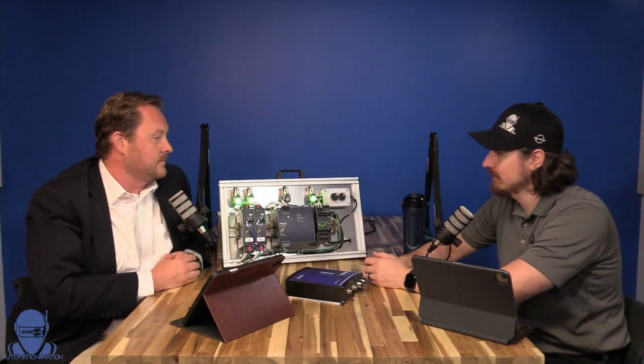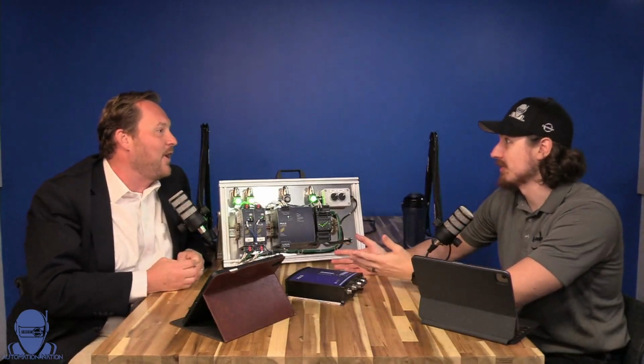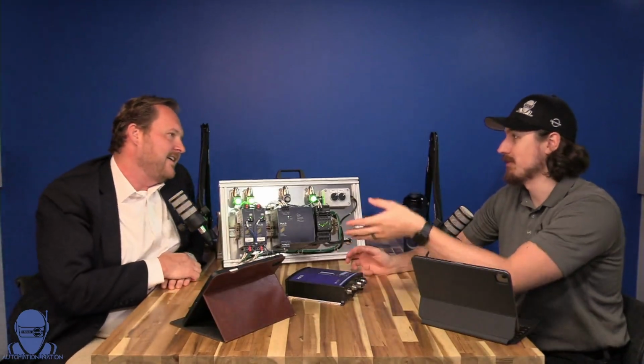Yep. You see the sensor array attached to channel 7 requires troubleshooting. You go out and troubleshoot that because you know exactly where to go, based on the manual of the machine I would imagine. Fix it. Try to reset it. If it resets, off you go. If it doesn't, maybe a little bit more work needs to be done. But at least you know where to go, instead of just, let's throw the guy at it and see what's wrong. Now you know. Exactly.